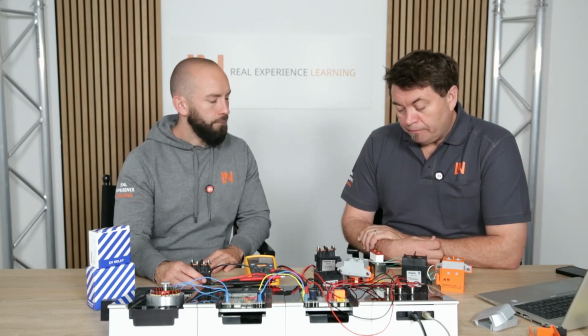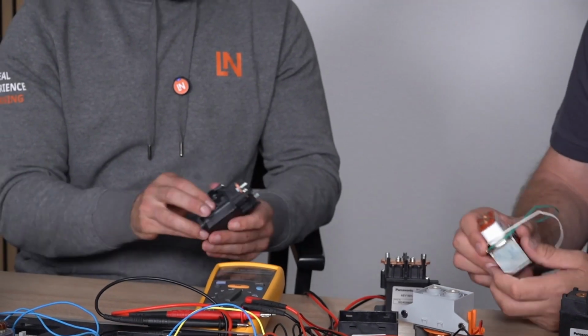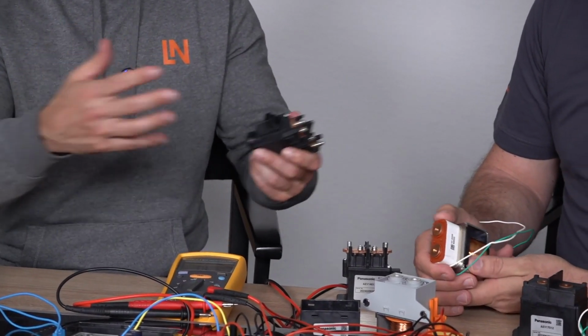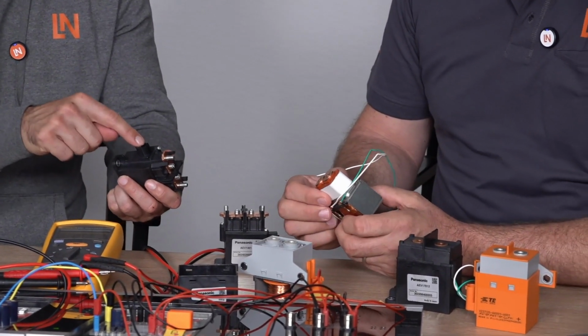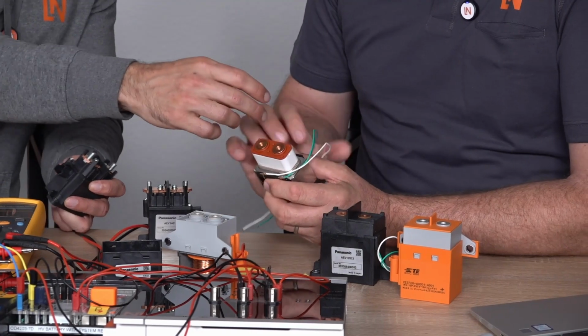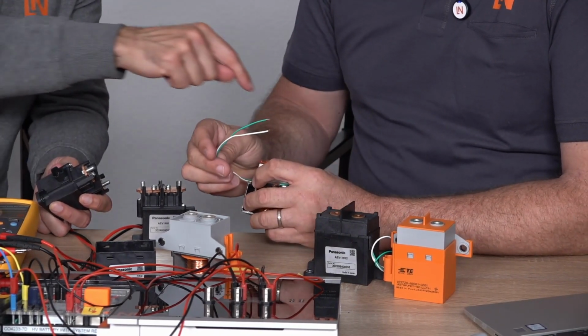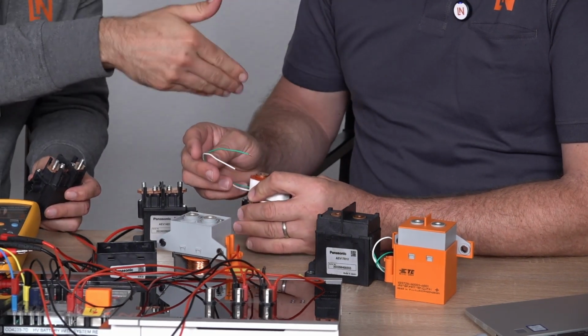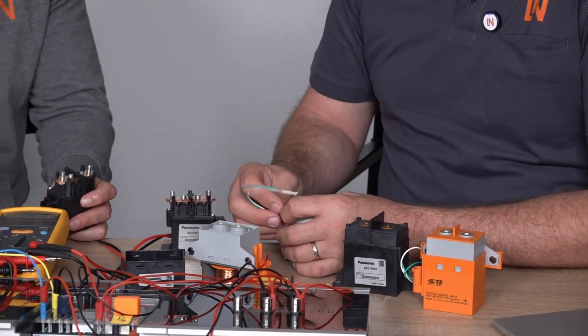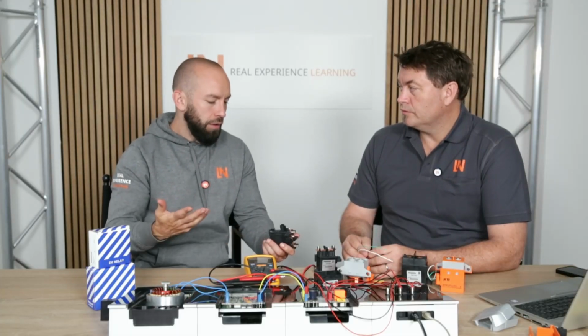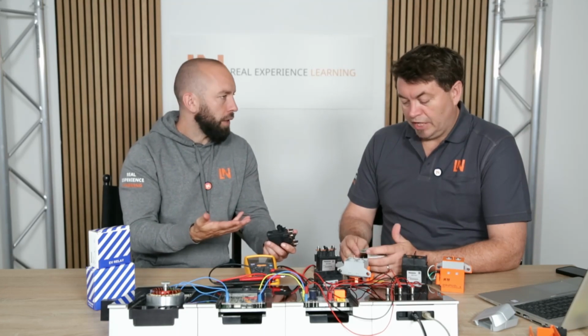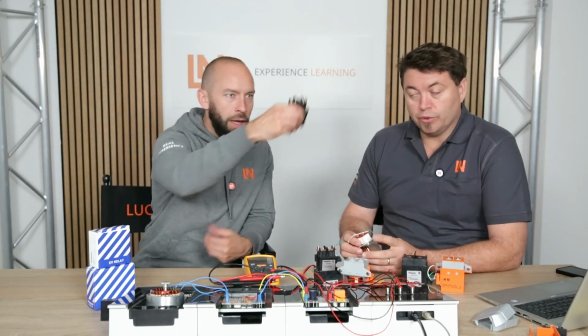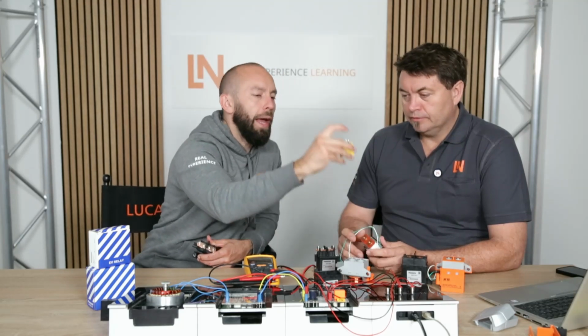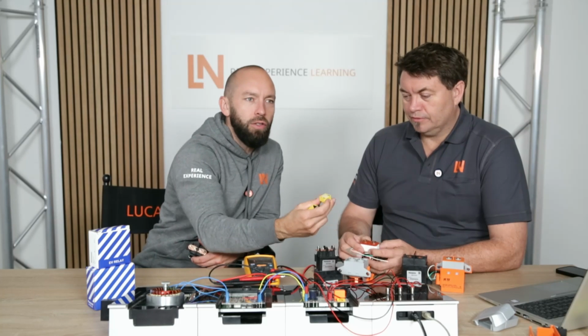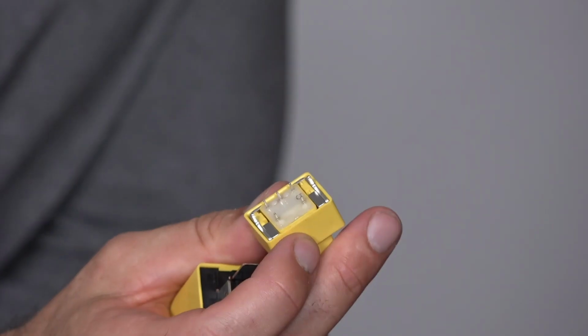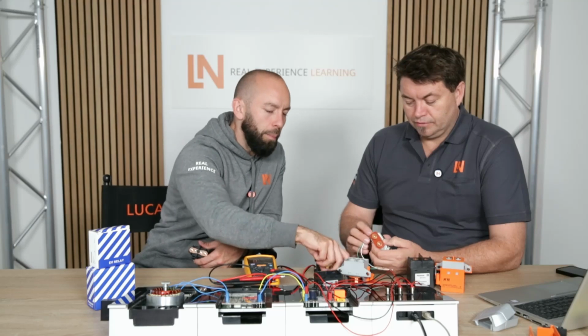Probably less complexity as well. But basically we can say all the relays, even when they have a different shape, have a low voltage connection as a control connection. They have a coil connected to the low voltage connection, and then a separated high voltage line where the drive current runs over - that's the simple setup of each high voltage relay. It doesn't matter if you take this one or this one. With contactors, because they're pretty small, we don't actually have high voltage running over it, but the basic thing is the same.